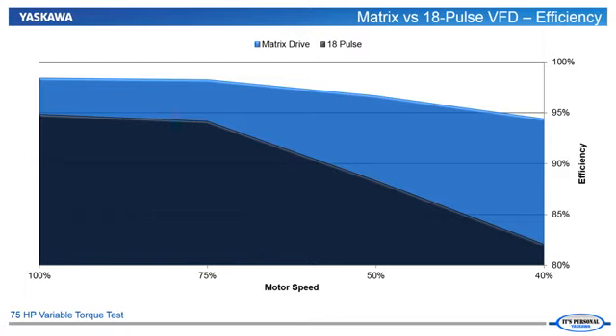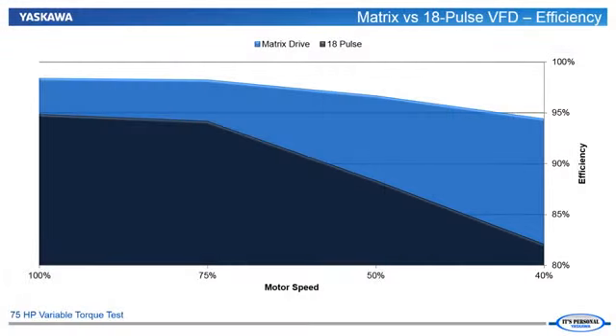At lighter loads, the 18-pulse drive's efficiency suffers greatly. The matrix drive is still 94% efficient at 40% speed, while the 18-pulse has dropped down to 82% efficiency. That is a 12% reduction in efficiency. That is money out of your pocket.